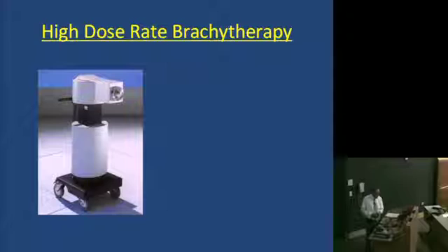So this is an example of a high-dose-rate brachytherapy unit where the iridium-192 sources are stored. We use this particular approach for treating gynecological cancers, prostate cancers, gastrointestinal cancers, and pulmonary cancers.